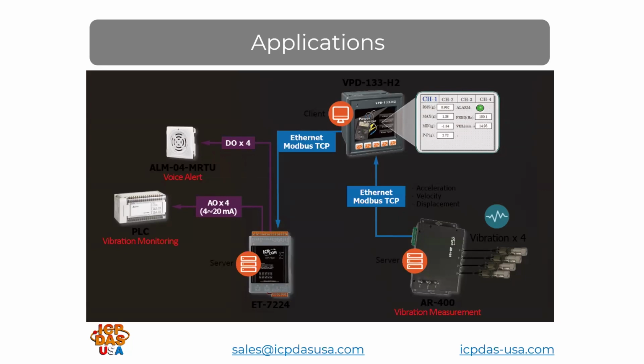In this case, the ISN 701 F15 L030 IEPE accelerometer captures vibration signals, and the AR400 accelerometer data logger calculates vibration features like peak-to-peak acceleration and RMS velocity. The AR400 converts these vibration features into corresponding current values. The ET7224 Ethernet I/O module receives the current values calculated by the AR400 accelerometer data logger via the VPD.